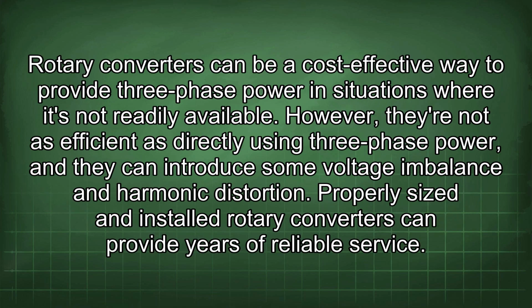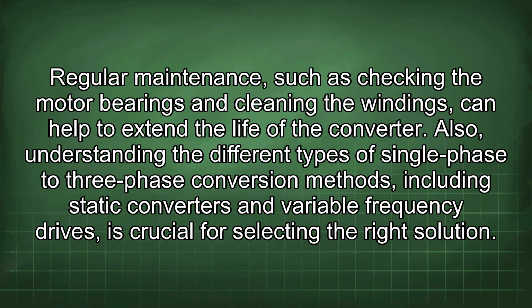Rotary converters can be a cost-effective way to provide three-phase power in situations where it's not readily available. However, they are not as efficient as directly using three-phase power, and they can introduce some voltage imbalance and harmonic distortion. Properly sized and installed rotary converters can provide years of reliable service. Regular maintenance, such as checking the motor bearings and cleaning the windings, can help to extend the life of the converter.